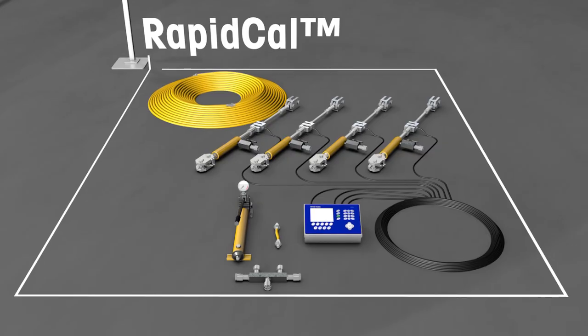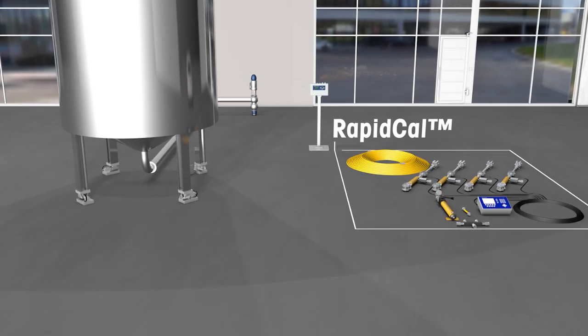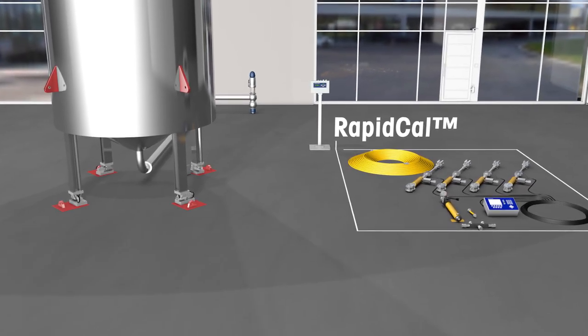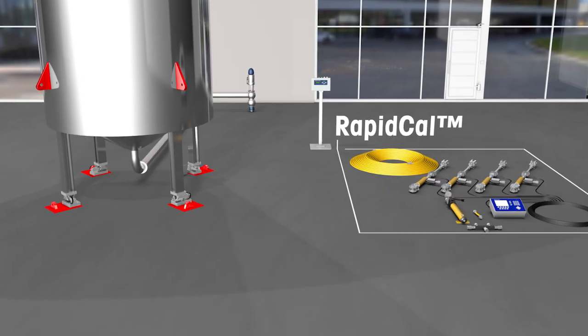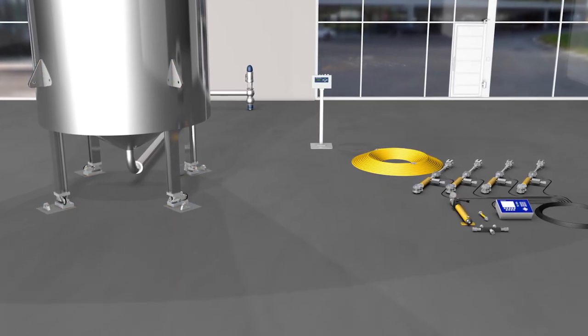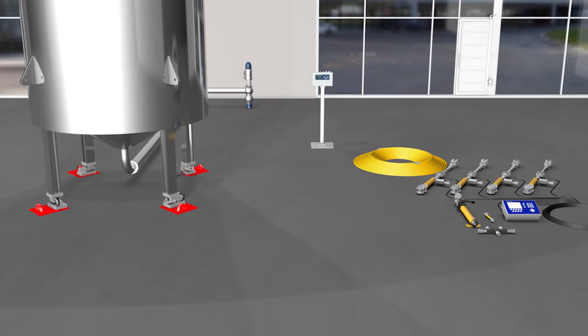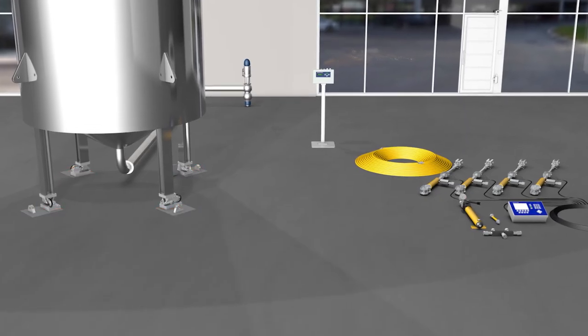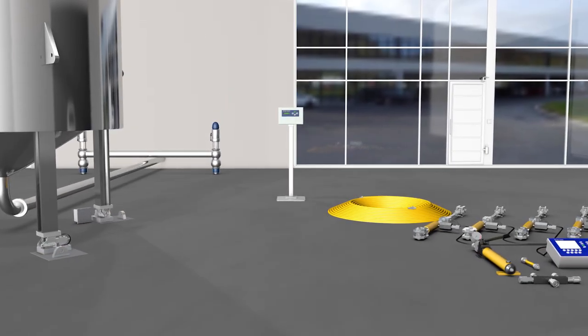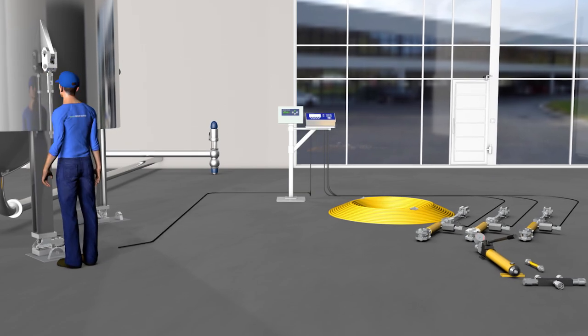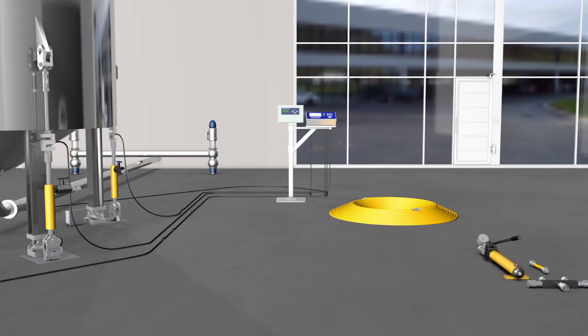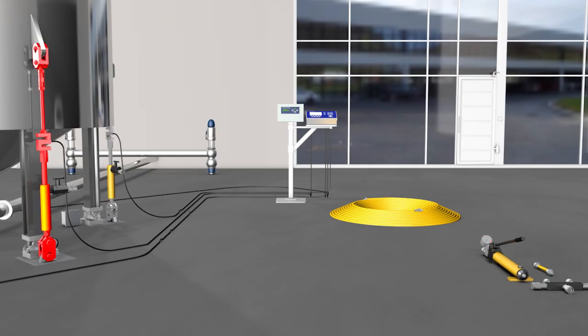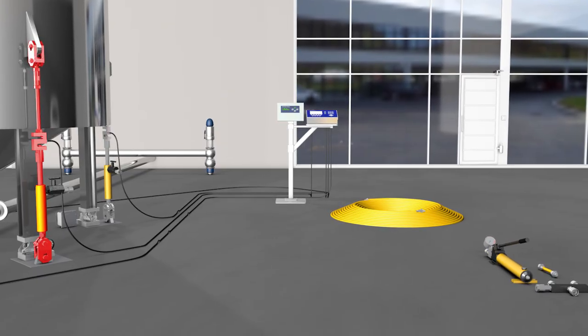We will bring the calibration equipment to your location. From you, we only need the attachment points on the foundation and on the tank. The RapidCal equipment is connected to the solid anchor point on the foundation. To attach the equipment to the tank, threaded rods are connected. The rod is mounted on the tank. The hydraulic cylinder and the reference load cell complete the calibration equipment.